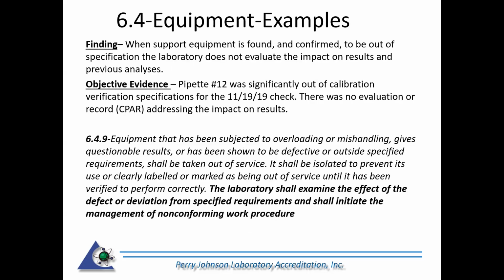Okay, another example: when support equipment is found and confirmed to be out of specification, the laboratory does not evaluate the impact on results and previous analyses. What we found here was that pipette number 12 was significantly out of calibration verification specifications for the 11/19/19 check. There was no evaluation or record addressing the impact on results. So here again, a pipette, which impacts the test results, had some issues, again, sub 649.